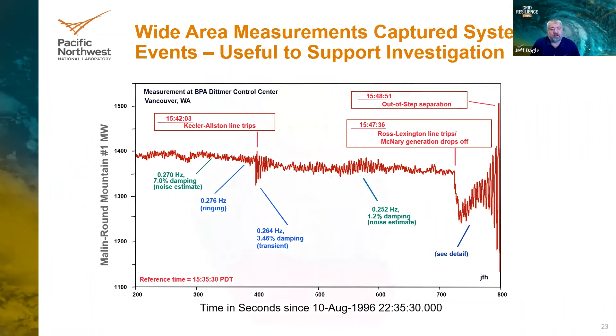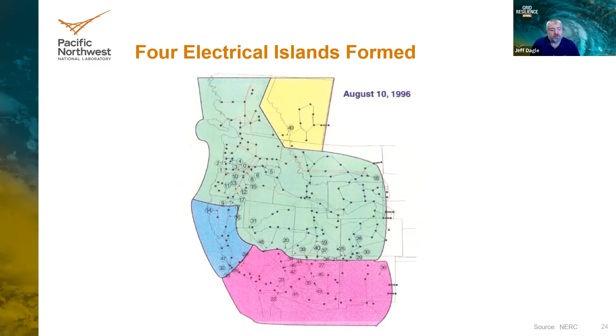Four electrical islands were formed as the Western interconnection broke apart. Depending on whether you were importing or exporting power before the event determined whether you had a big blackout. California and Arizona areas were importing a lot of power, so they took the brunt of the outage across the Western interconnection, affecting about 30 million people that day. The root cause was that tree trimming near the transmission lines wasn't maintained well enough, causing a ground fault with the lines getting into the trees and tripping off. But this is a big one.